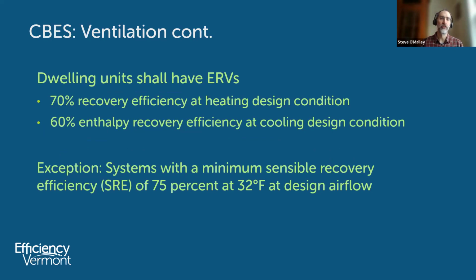CBES also says that dwelling units shall have ERVs, and that ERVs shall have a 70% recovery efficiency at heating design and a 60% enthalpy recovery efficiency at cooling design conditions. And they do have an exception: systems with a minimum sensible recovery efficiency of 75% at 32 degrees Fahrenheit at design airflow. What I think they're getting at is, if you really wanted to install an HRV instead of an ERV, just make sure your HRV is 75% efficient on the recovery efficiency side. I think that's the intent there.